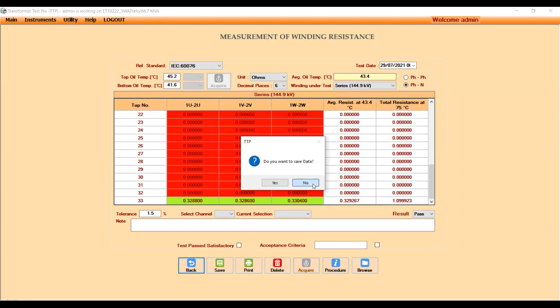And how do you get these values for the winding resistance? Very simple, again, as I explained for voltage ratio. Similarly, there is a button at the bottom called Acquire. You click on this, and the values for the winding resistance get populated in this table automatically. I click on the back button here, and let's go back to the test list.